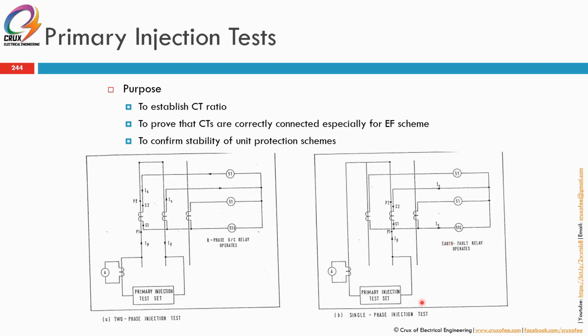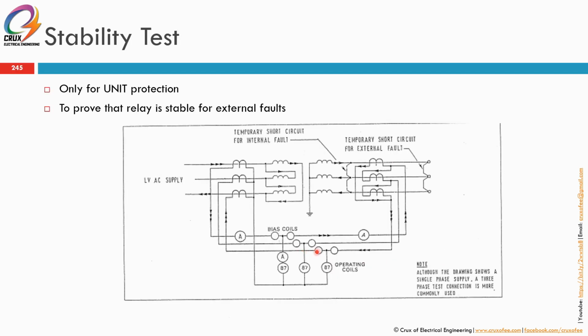Alright. So for stability test, normally you will use the primary injection to test before the CT and after the CT, which is to test within zone and out of the zone. So that is the stability test using primary injection for differential protection scheme. So this is a stability test. It's only done for unit protection or differential protection, to prove that the relay is stable for external faults.